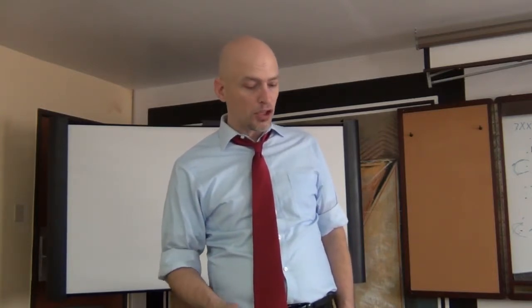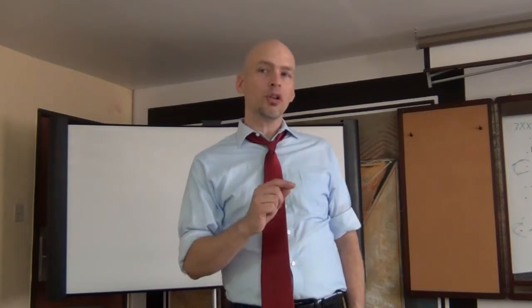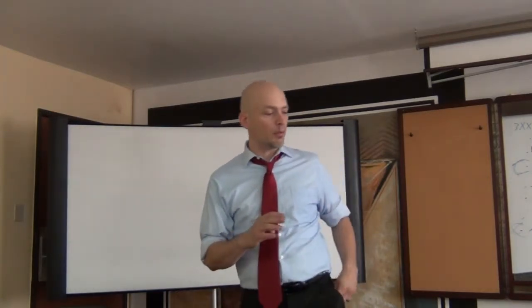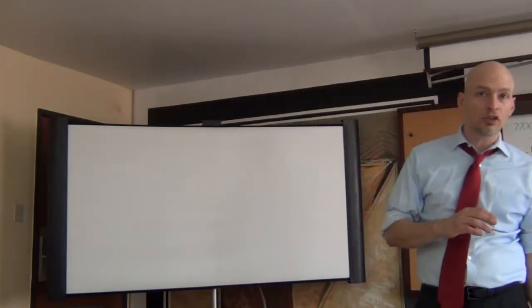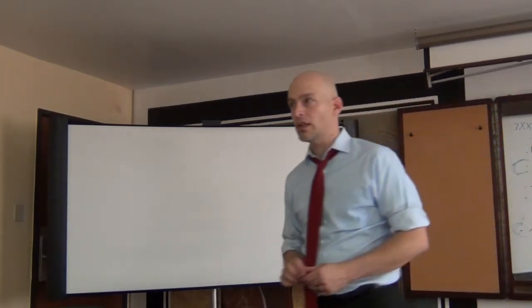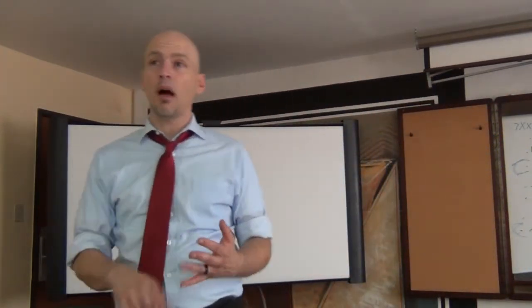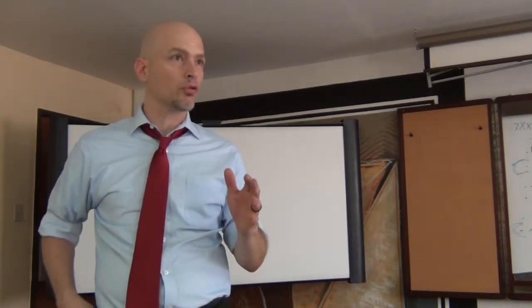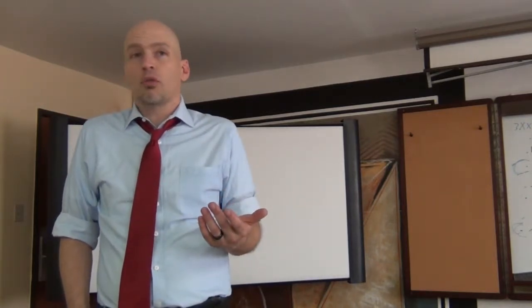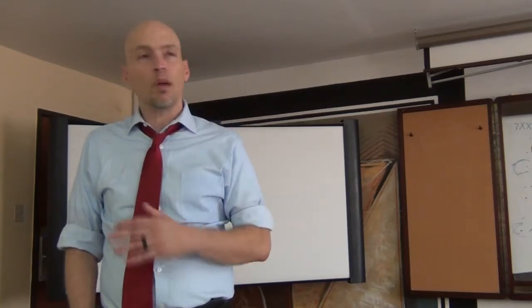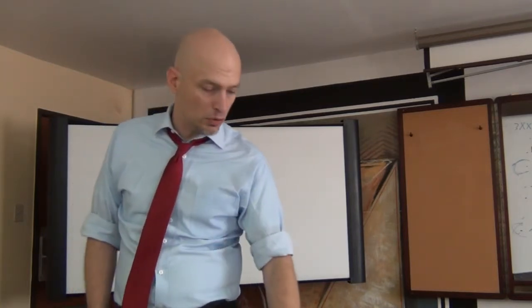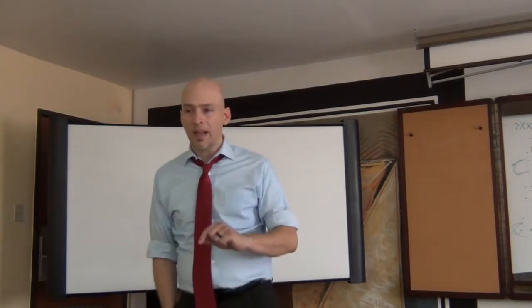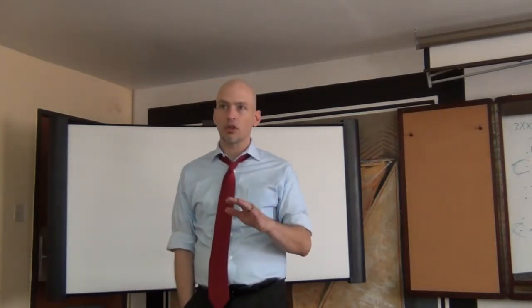Show windows under G2. Again, commercial lighting, guys, if it's in a commercial occupancy and they don't tell you it's not continuous duty, consider continuous duty. That includes track lighting, spot lighting, window lighting, show window lighting, anything of that nature. If it's a commercial establishment, retail stores are going to be open for 8 to 12 hours a day. It's way past your 3-hour minimum. It's continuous duty. So put yourself a note. It's 200 VA per linear foot times 125%.